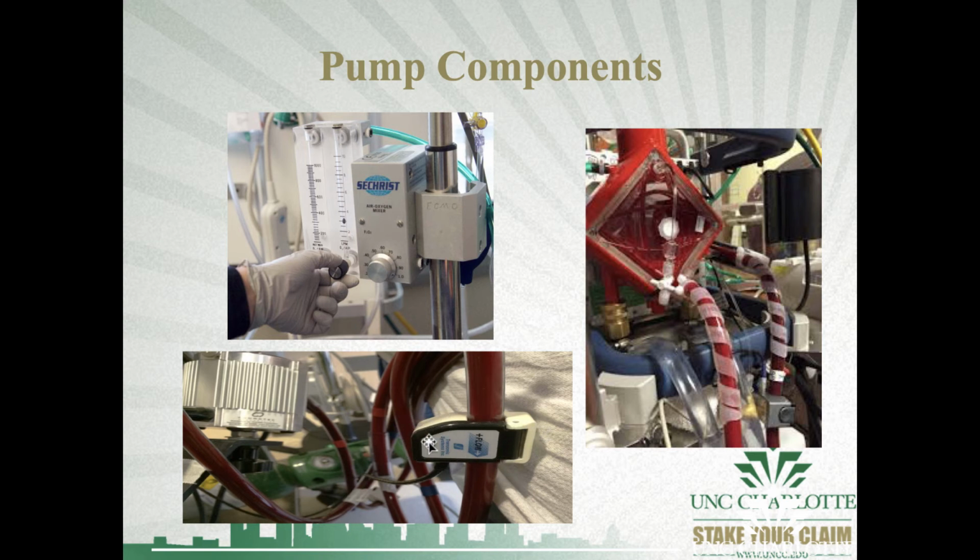They also provide parameters that are shown on the screen. Hopefully I have a picture of the screen. I don't think I do. And it'll show your flow rates. It'll also show you your delta pressure. So you always want to know what your pressures are between this area and other areas throughout the system to gauge the health of your circuitry and your system.